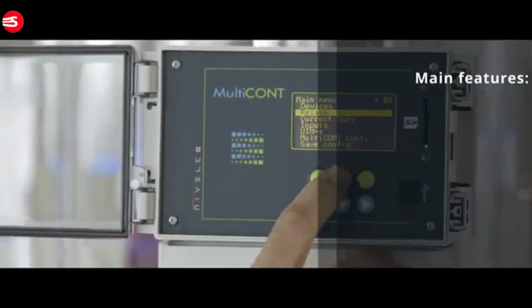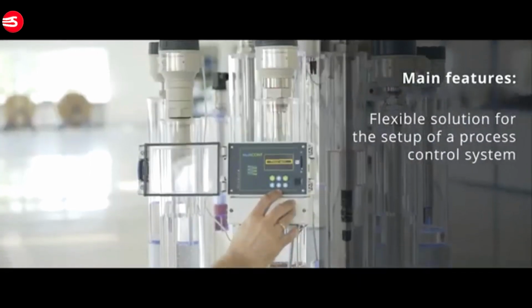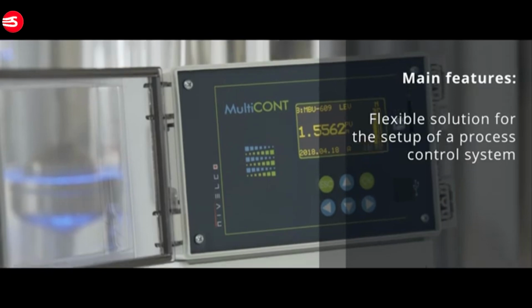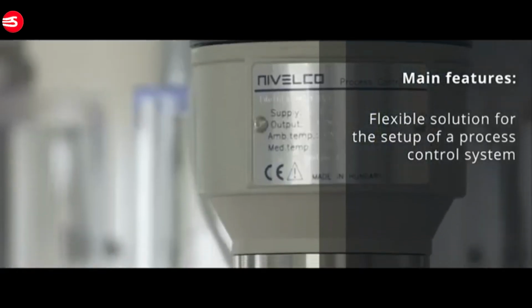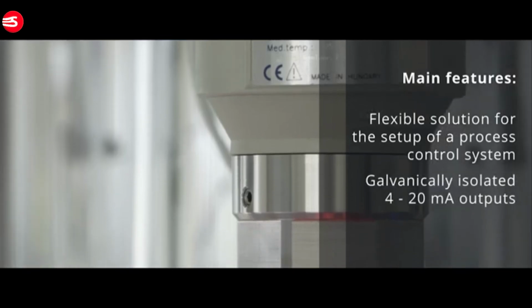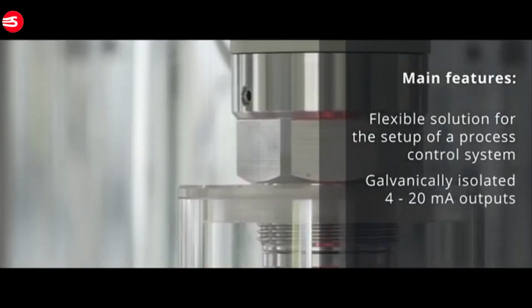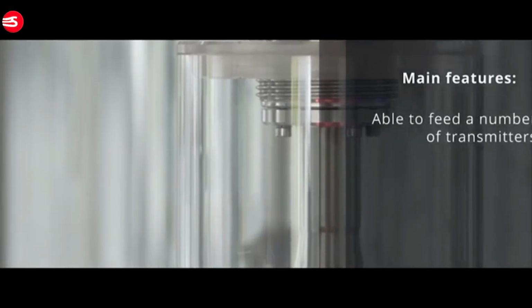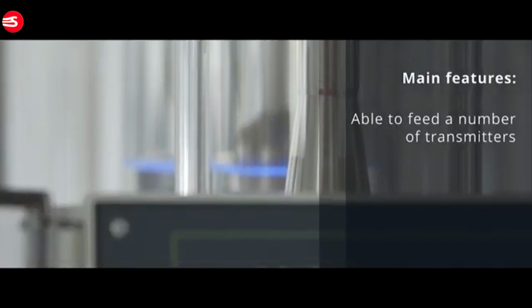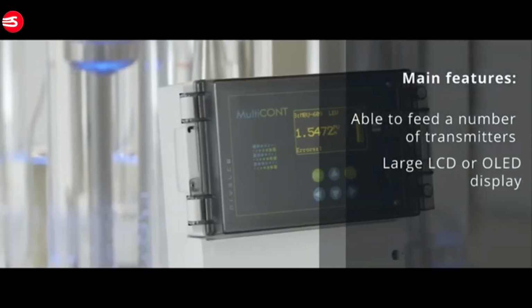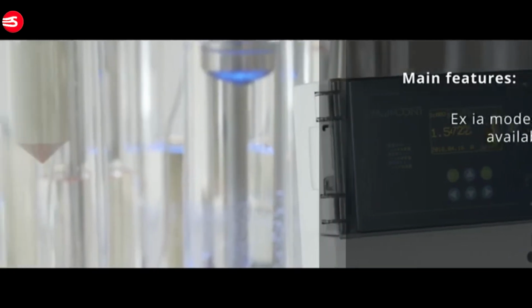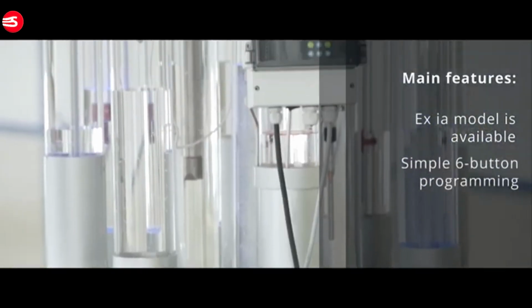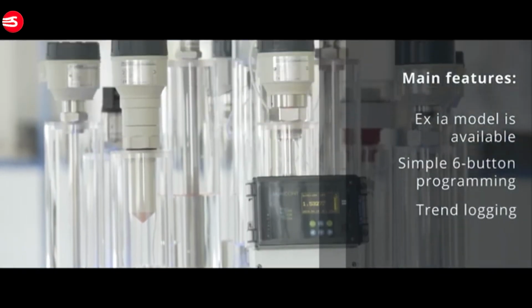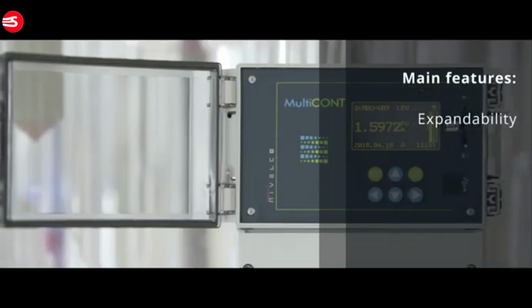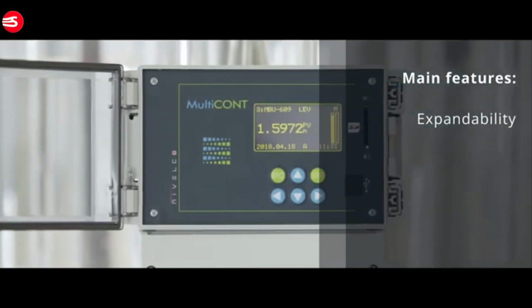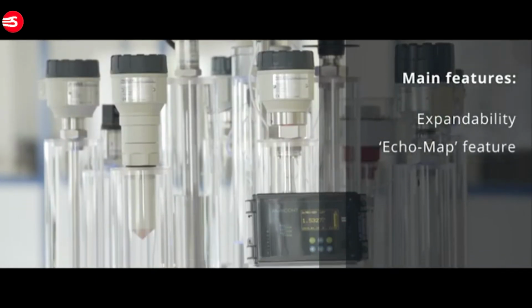The main features of Multicont are the following: flexible solution for commissioning a process control system consisting of NIVELCO's HART-based intelligent level, temperature or pressure transmitters, galvanically isolated 4 to 20 mA outputs assignable for the transmitters, can feed up to 15 standard or a maximum of 4 Ex ia rated transmitters, highly informative large LCD or OLED display, Ex ia model is available, simple 6-button programming, trend logging into internal memory or external SD memory card, expandable with universal interface modules via RS485 line, Echo-Map for EchoTREK and EasyTREK ultrasonic transmitters.